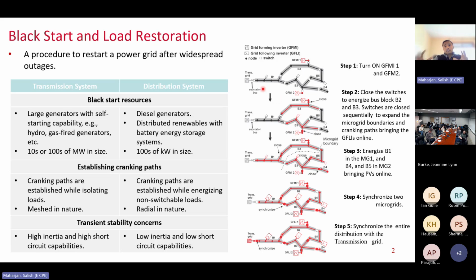Okay. Firstly, there's a blackout in the distribution system because there's a transmission grid outage where it was connected. So there are no active sources at that time, right? The first step is to switch on the black start resources. Black start resources in the case of DERs are generally grid forming inverters. In this case, we have two grid forming inverters located at this point and this point, right? After switching them on, we are able to energize the neighboring bus blocks. In this case, we have 5 bus blocks, and out of the 5 bus blocks, we can energize B2 and B3 at a time.